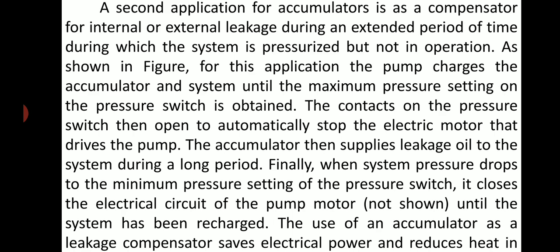The accumulator then supplies leakage oil to the system during a long period. Finally, when system pressure drops to the minimum pressure setting of the pressure switch, it closes the electrical circuit of the pump motor until the system has been recharged. The use of an accumulator as a leakage compensator saves electrical power and reduces heat in the circuit.